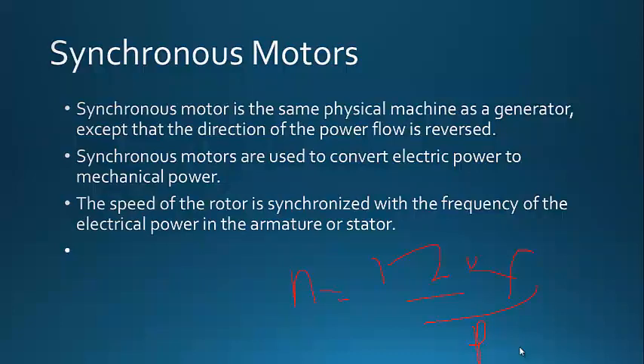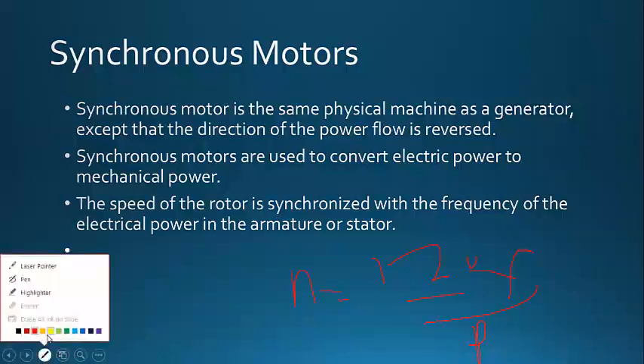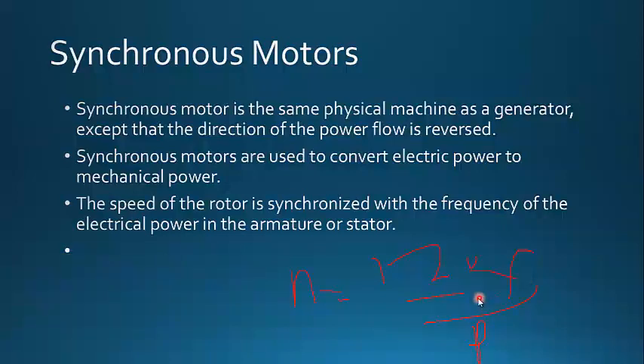The speed of the rotor is synchronous with the frequency of the electrical power in the stator. The speed of a synchronous motor is always proportional to the frequency of the power supply. We operate at a frequency of 50 Hz, so if we connect a synchronous motor to this 50 Hz supply, irrespective of the load connected to it, the speed of the motor will never change. The only parameter that can change the motor speed is the frequency. The speed relationship is: Speed = (Frequency × 120) / P, where 120 and P are constants, so frequency is the only variable.